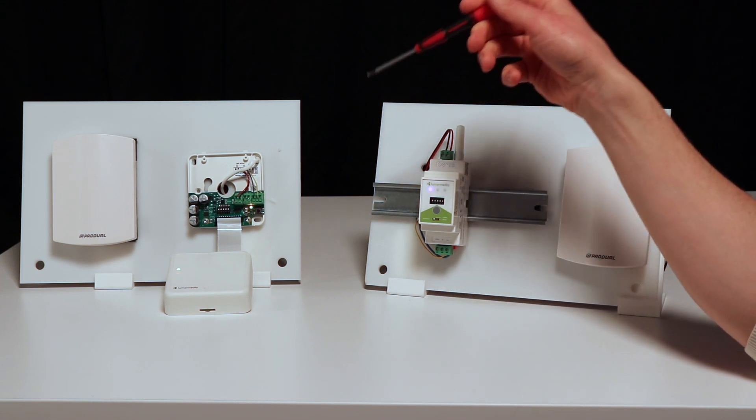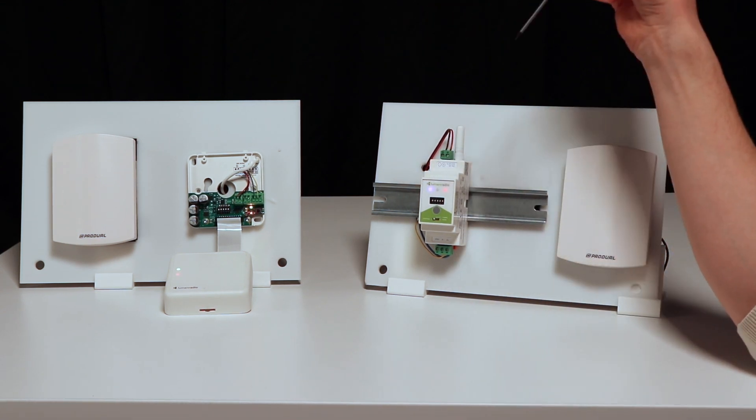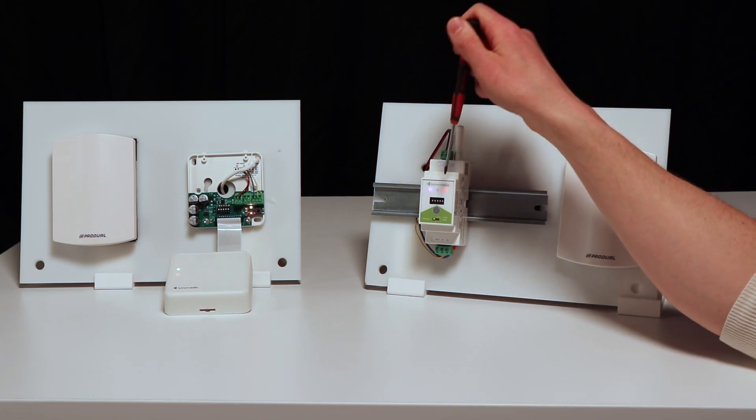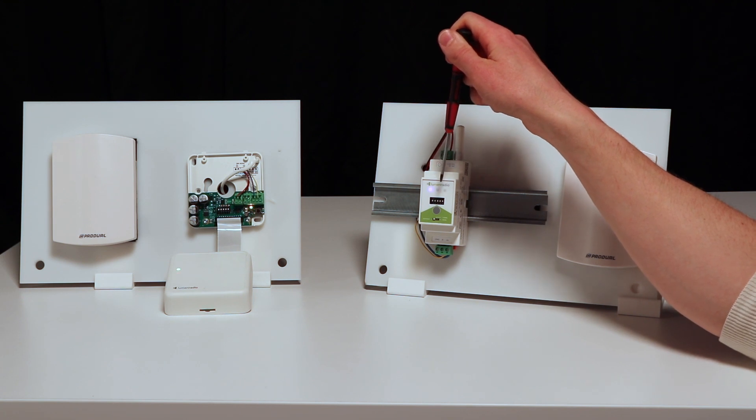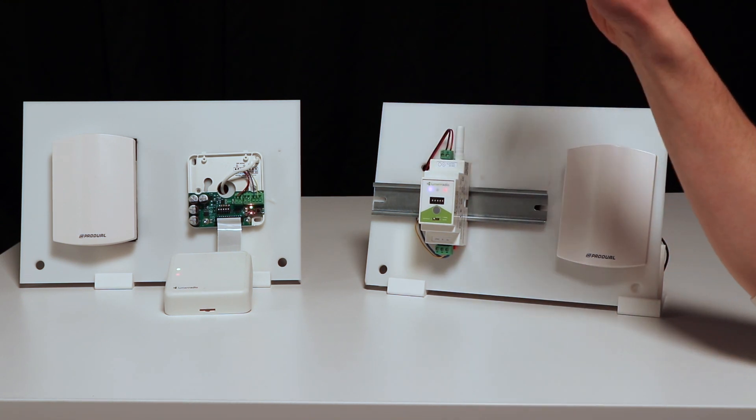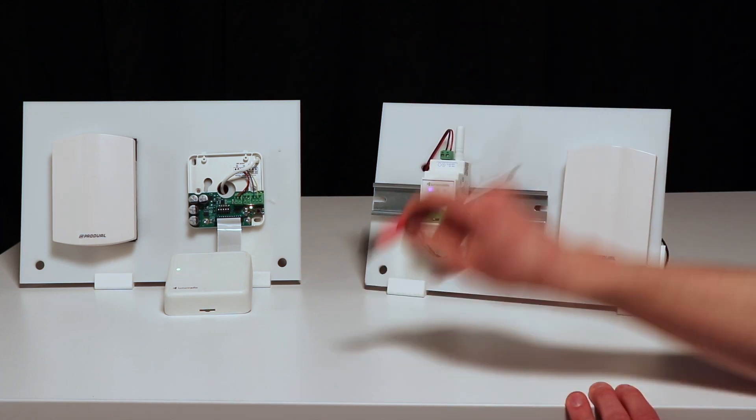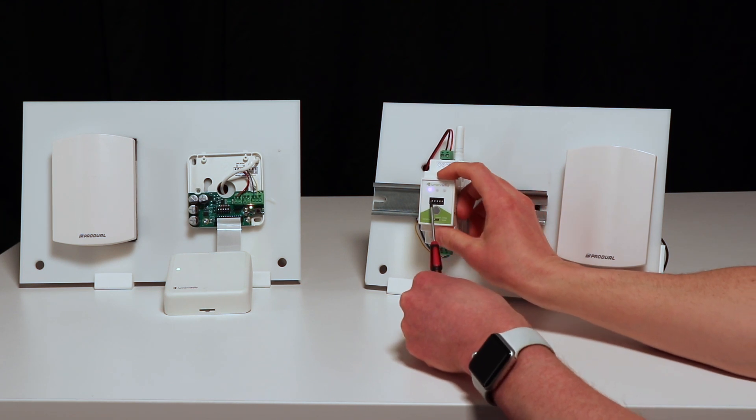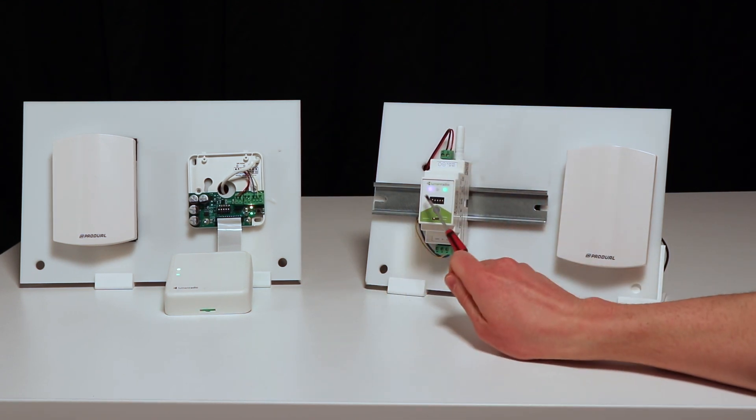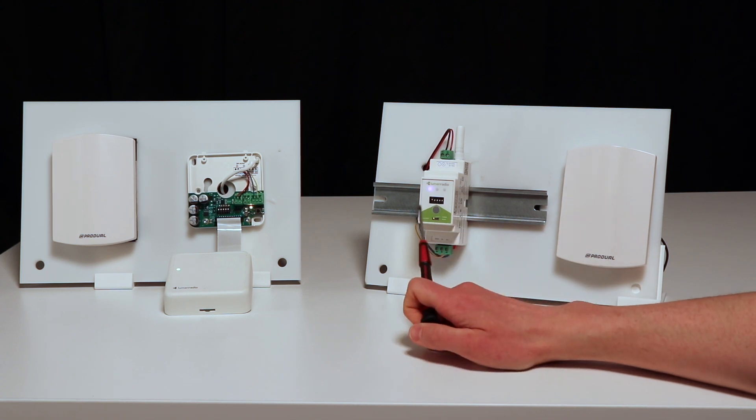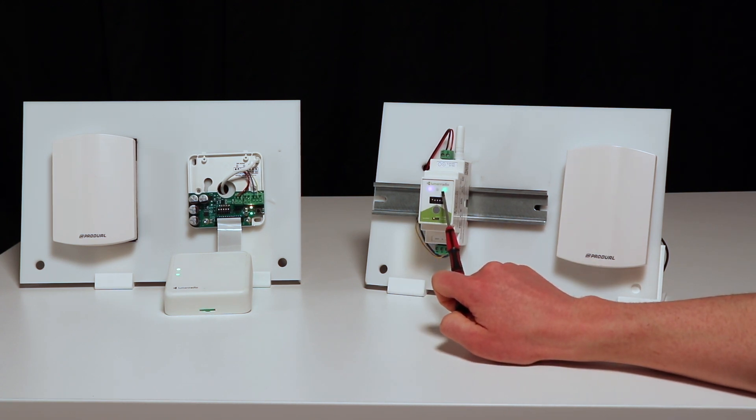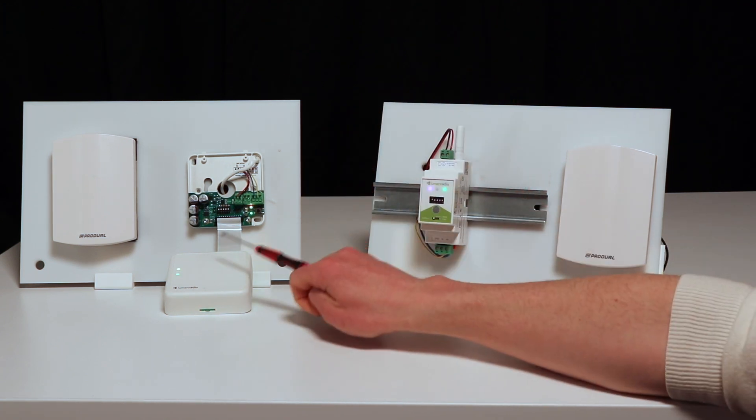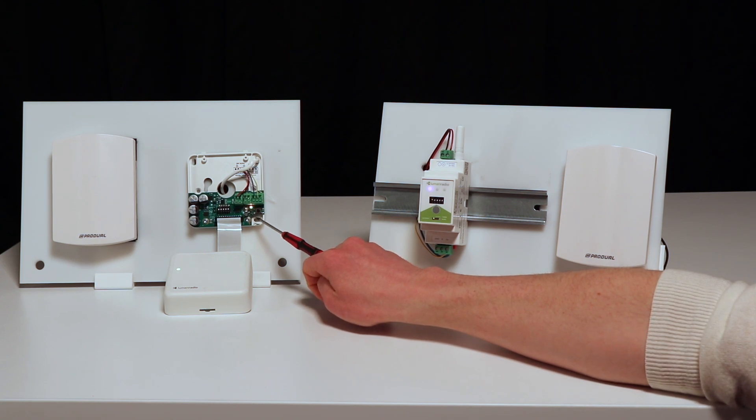In this case, it is that we have set the wrong baud rate. The pre-configured initial baud rate will always be 9600 with no parity and one stop bit. Our BACnet sensors today are actually with 38400, so once I've turned the gateway to 38400, the RS-485 bus turns green and it will actually wirelessly transmit that configuration over to the nodes where you see that the node is already green.